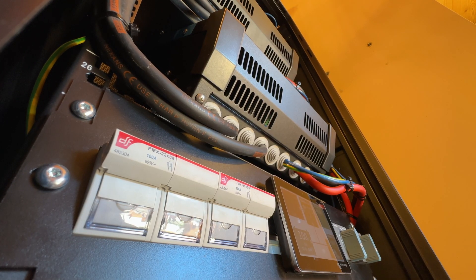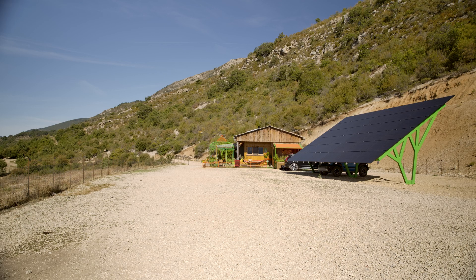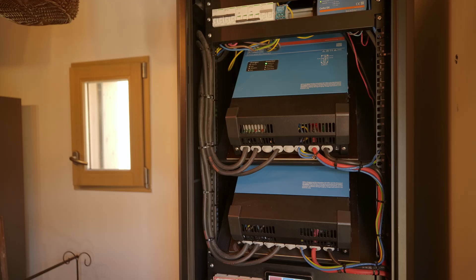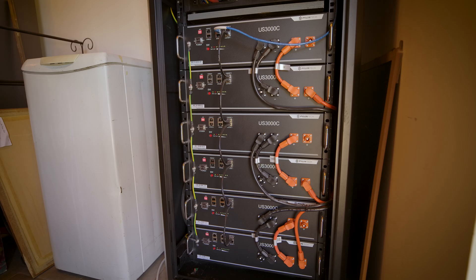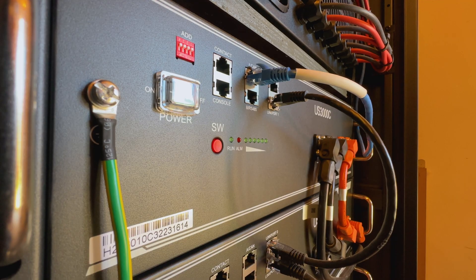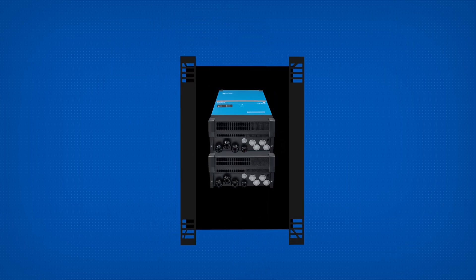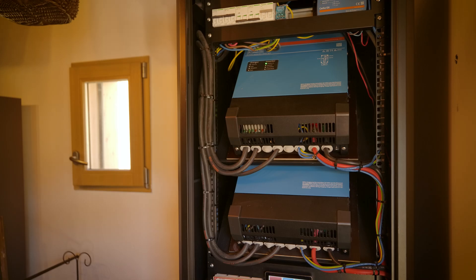I installed a 10 kVA single-phase system with 13.5 kilowatts peak of PV modules. We chose to install a system in a 19-inch rack using lithium batteries that allowed us to put everything inside. It was also a necessity because of the temperature. Stefan has ensured the units in the rack system don't overheat by creating good natural ventilation on all sides by mounting them at an angle, which avoids having to use fans.